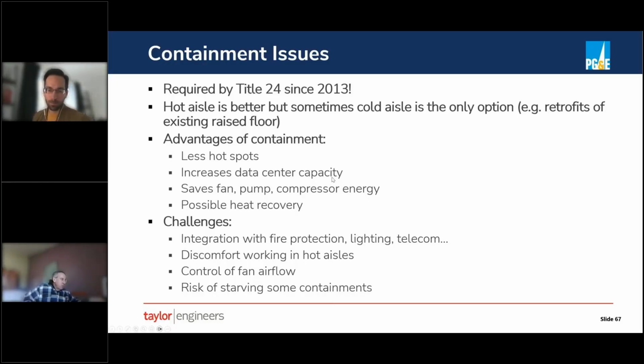Saves fan, pump, compressor energy, heat recovery. We'll talk about that on Wednesday. But when you have containment, as I said, you can run at higher supply temperatures and return temperatures, which opens up all kinds of opportunities for heat recovery. There are some challenges: integration with fire protection, lighting, and telecom. So if you're adding walls and lids and things to your data center, you need to make sure that your fire sprinkler system has the proper coverage. If it's a retrofit, this often means adding a sprinkler head. Your light fixtures, if it's a retrofit, you may need to add new lights because you're adding walls basically.